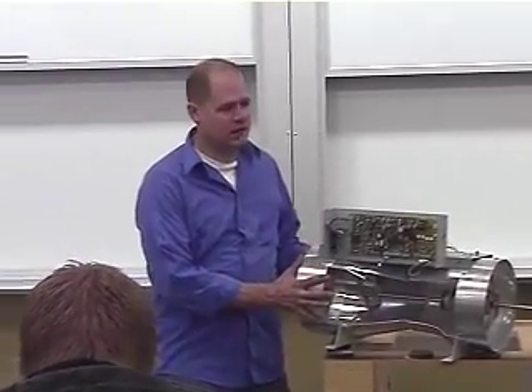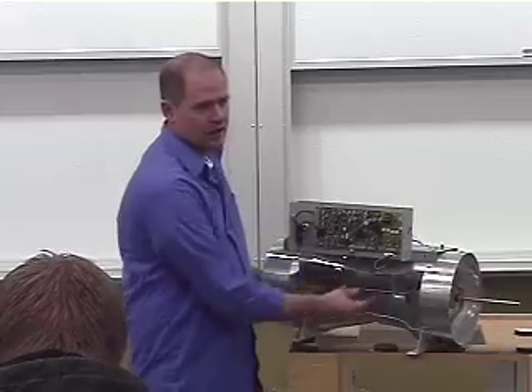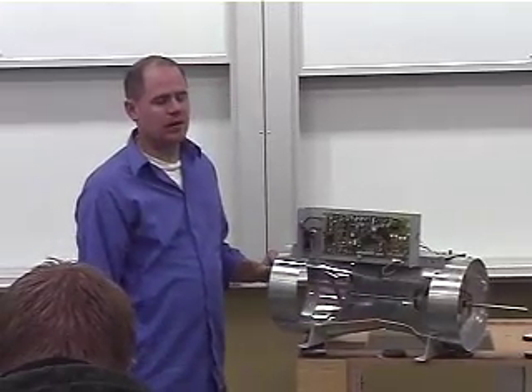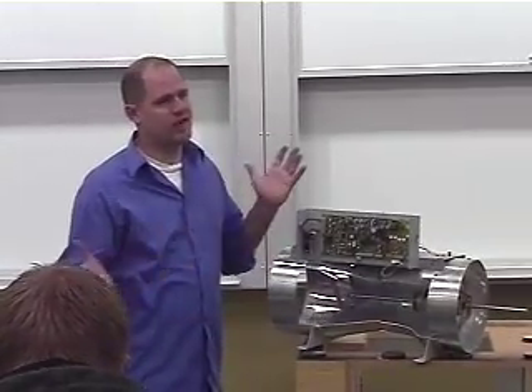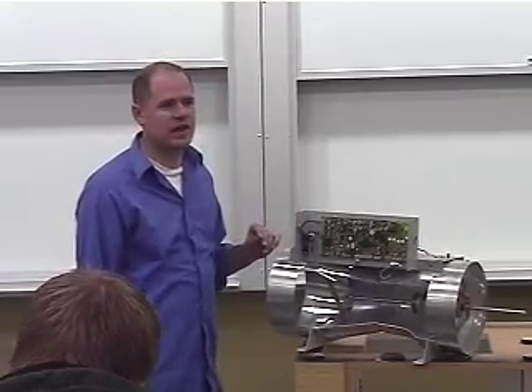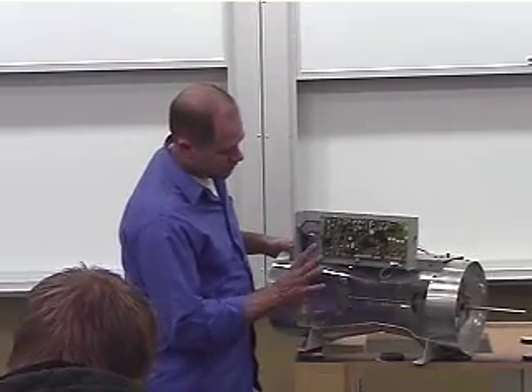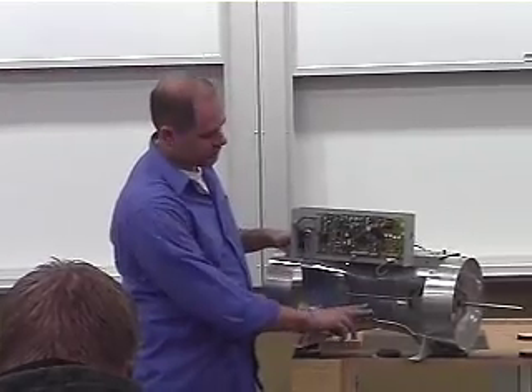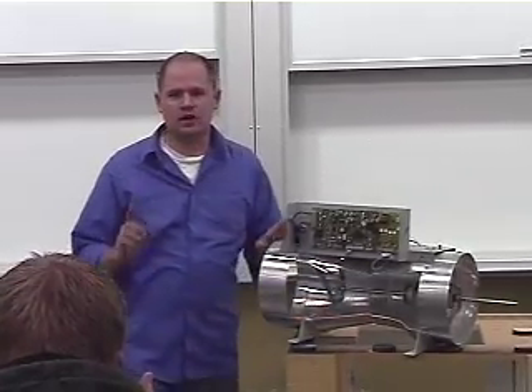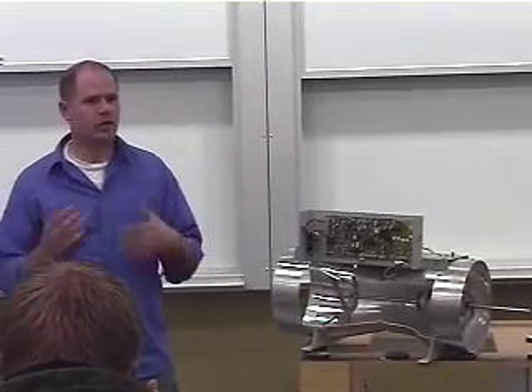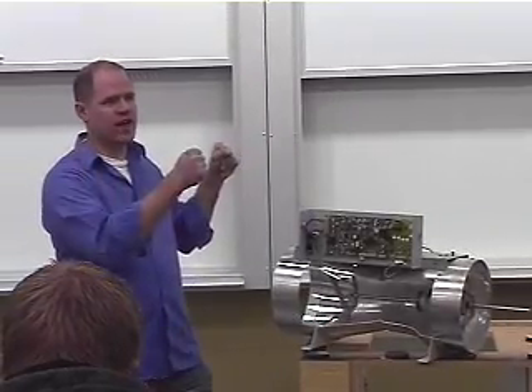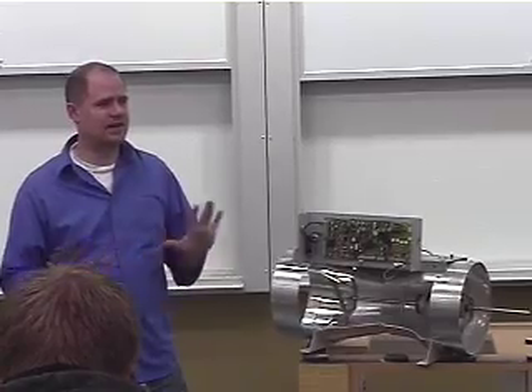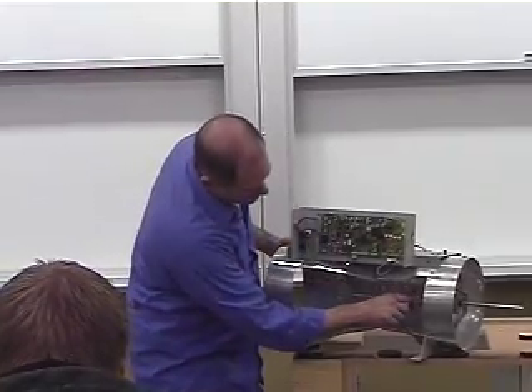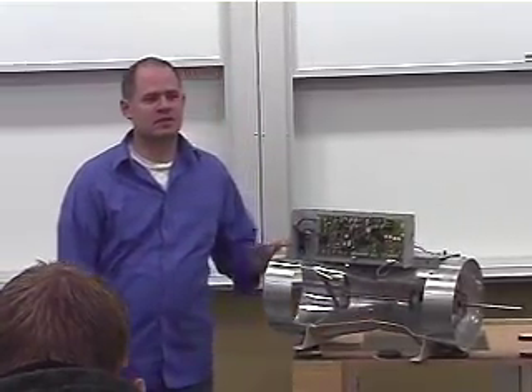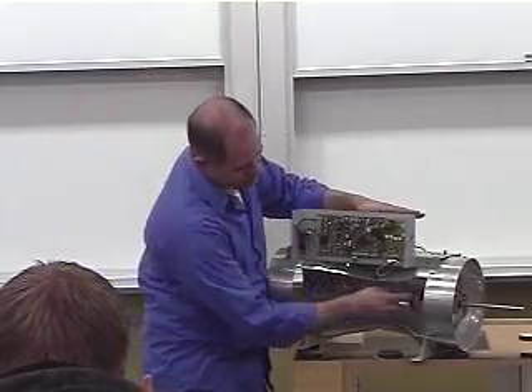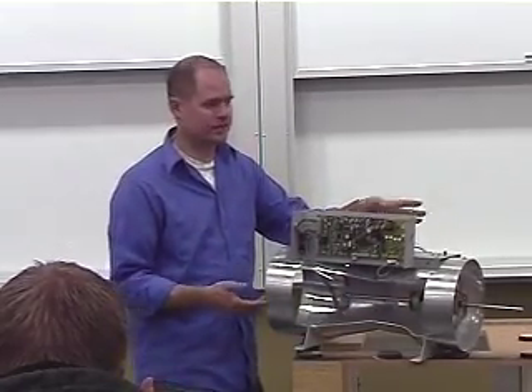The valve body and the cone assembly and everything in here has quite a bit of cost to it because of all the patents and the design and the machine processes they use and that kind of stuff. Another thing that I forgot to mention earlier, they are designed either to be vertical or horizontal only, one or the other. You can't take a horizontal valve and turn it vertical or anything like that, because this spring has to be a little bit different in those. Because in this path, the spring has no weight sitting on it.